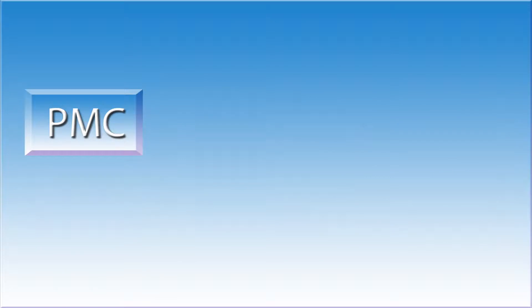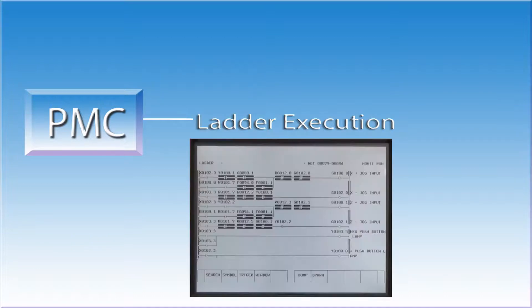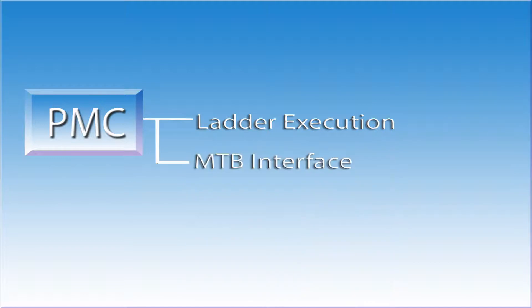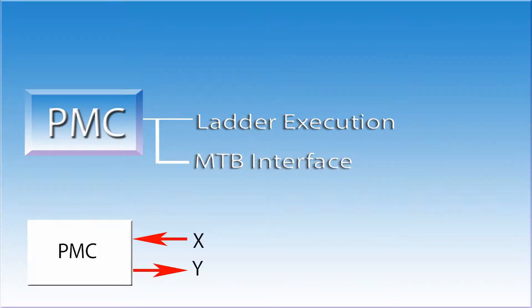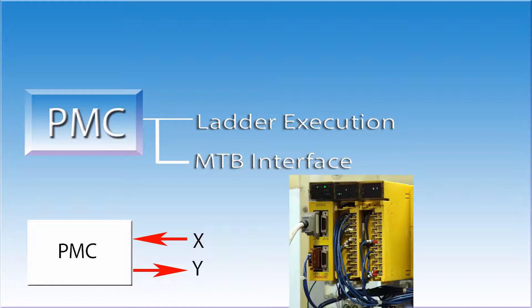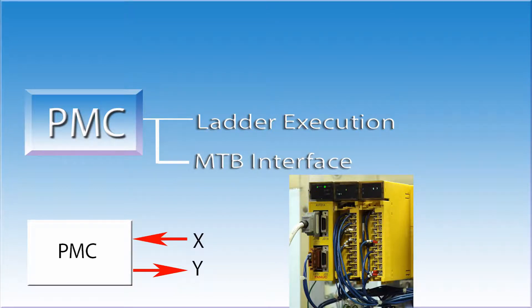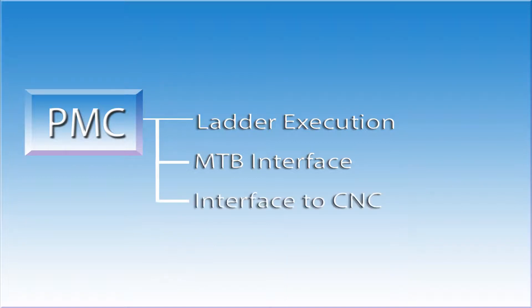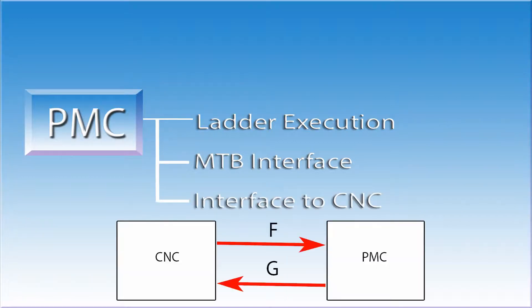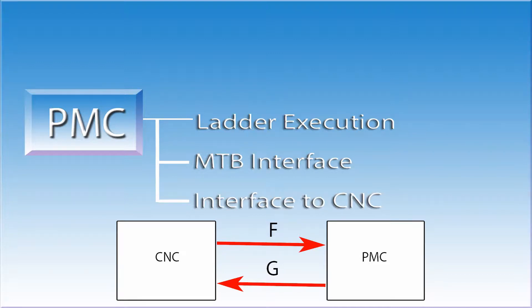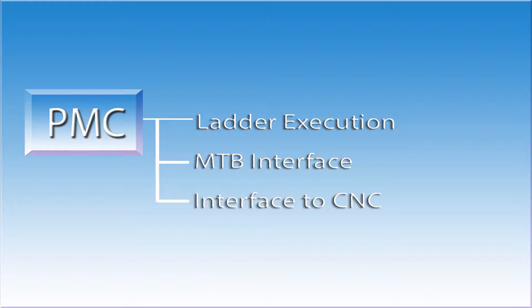The PMC also has four areas of responsibility. The first responsibility is ladder execution. It reads and executes the ladder logic commands that are created by the machine tool builder. The second area is the machine tool builder interface. The PMC talks to the machine through inputs and outputs. I call these real world devices because you can put a meter on a wire someplace and measure the actual signal. The third area of responsibility for the PMC is the CNC interface. Remember, the CNC and the PMC are always talking to each other. This is how the CNC finds out what is going on in the real world and the PMC sees what the CNC wants to see happen.